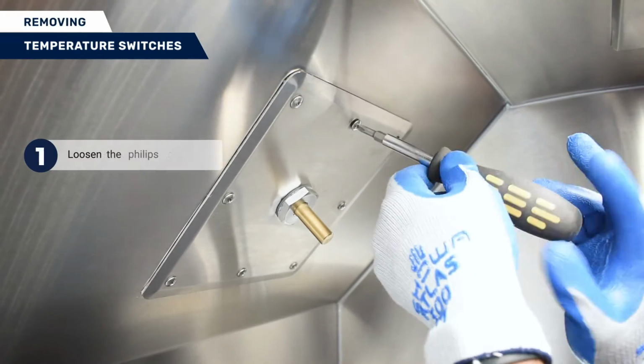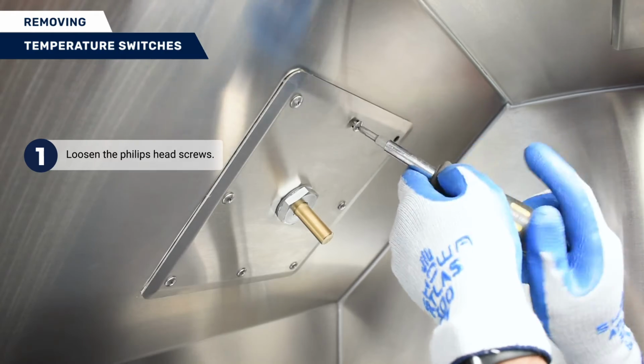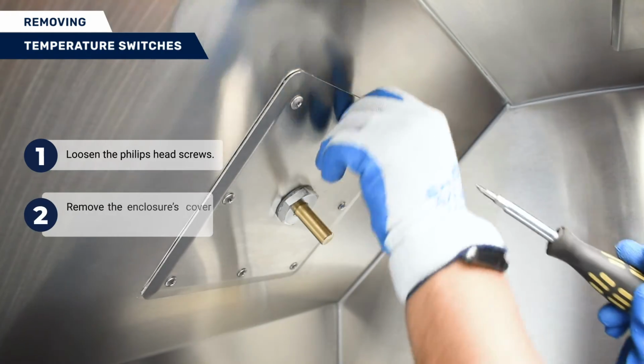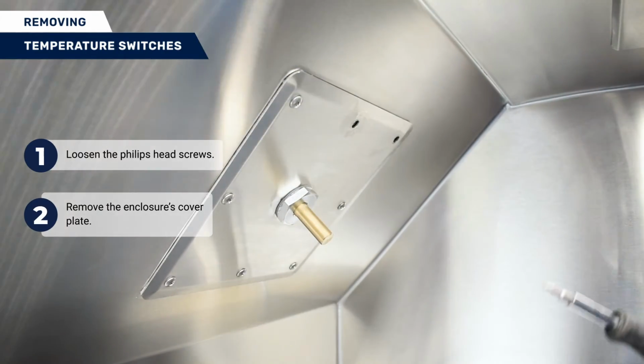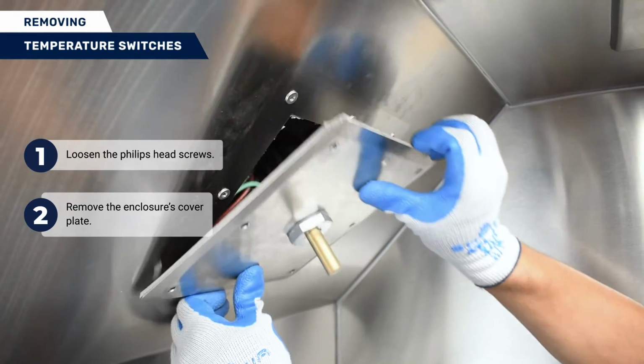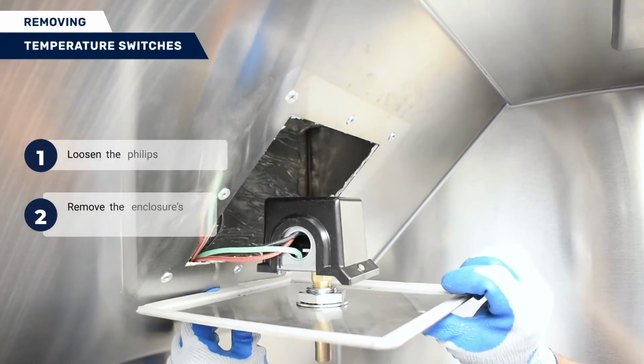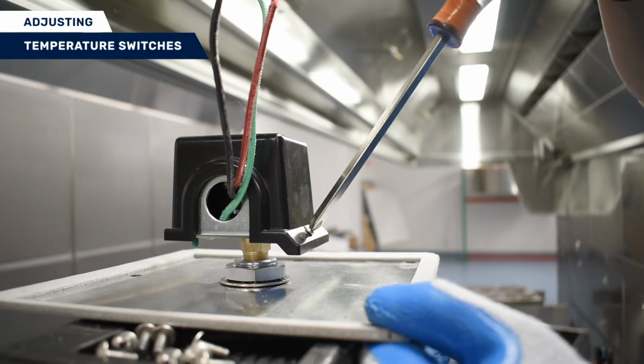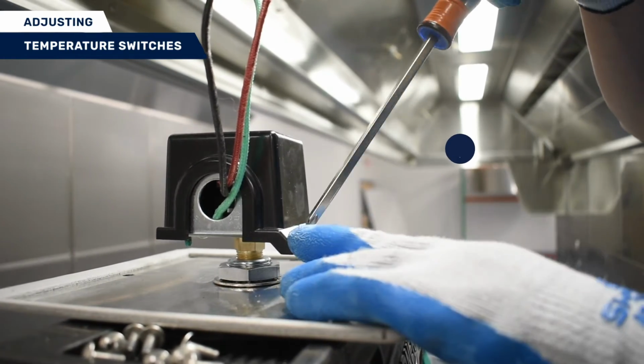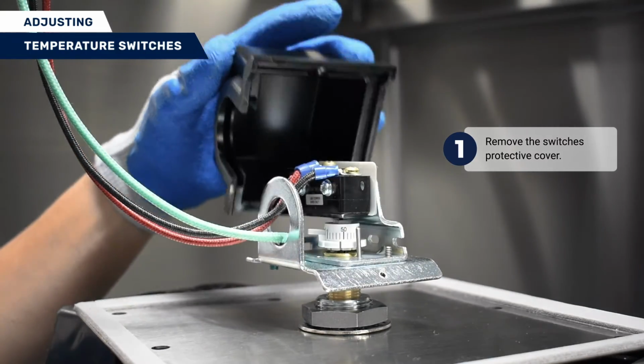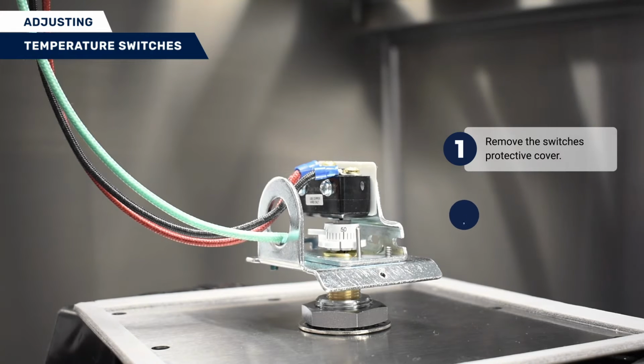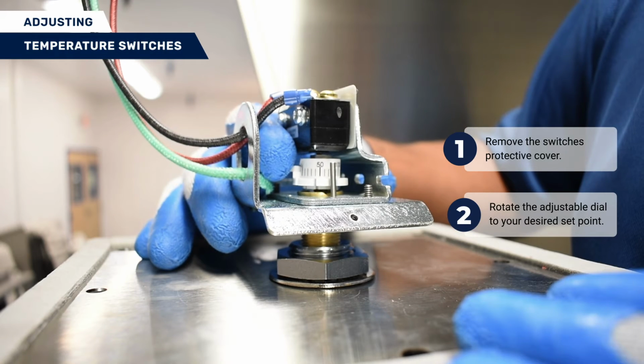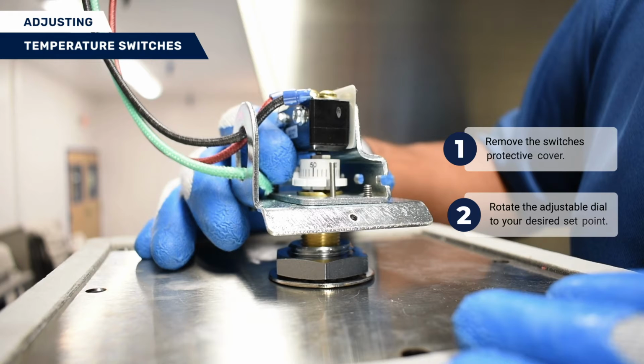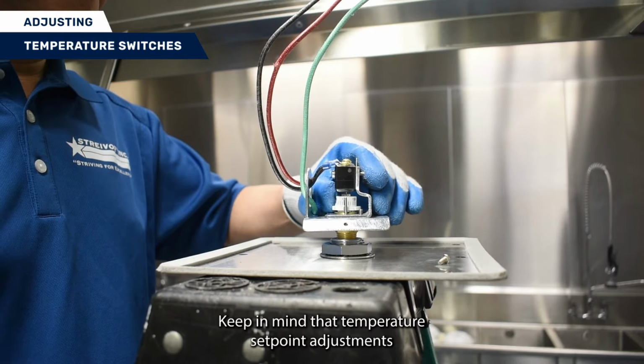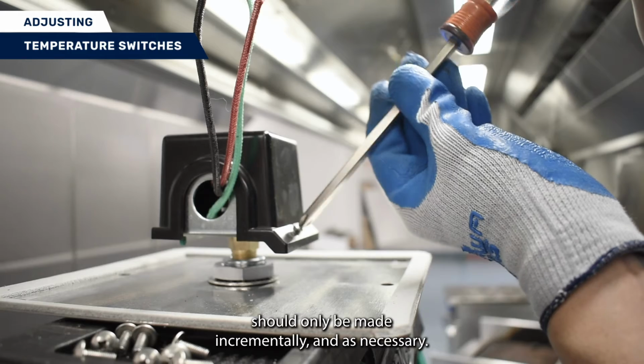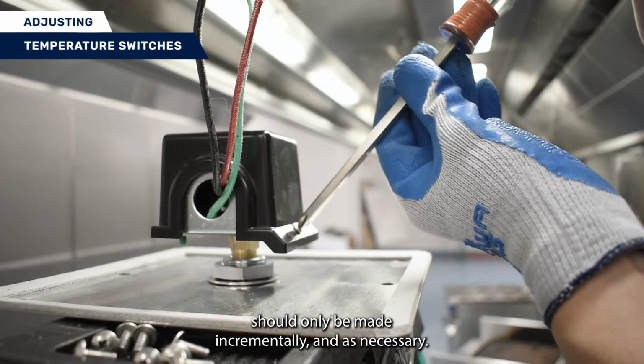To access or remove a temperature switch from its enclosure, remove the enclosure's cover plate by loosening the Phillips head screws. Be careful not to lose any of the screws. Then, if you need to adjust the temperature set point, remove the protective cover. Next, simply rotate the adjustable dial to your desired set point. Keep in mind that temperature set point adjustments should only be made incrementally and as necessary.